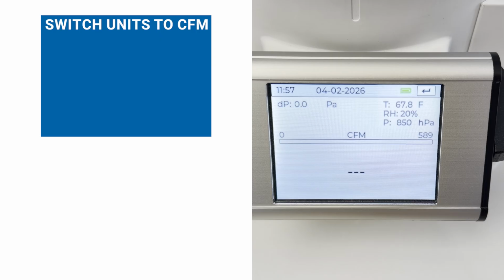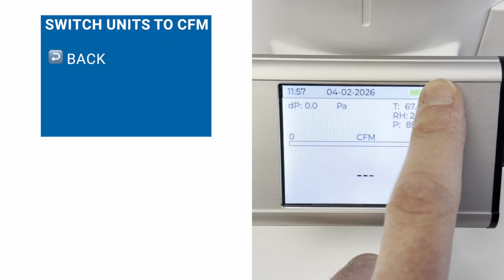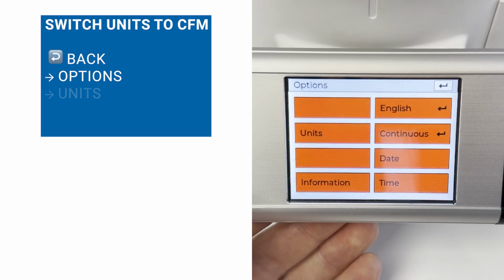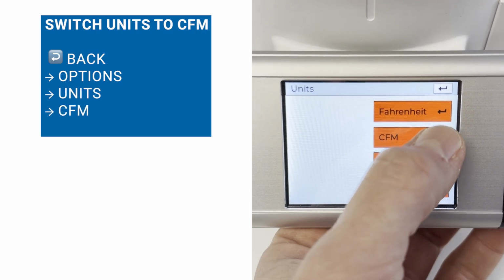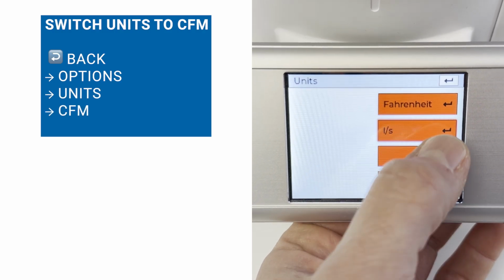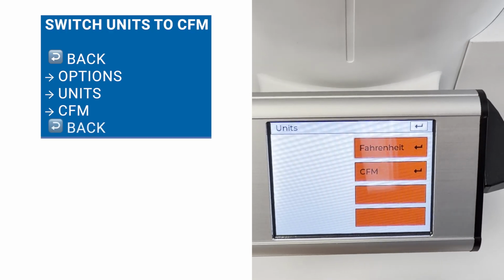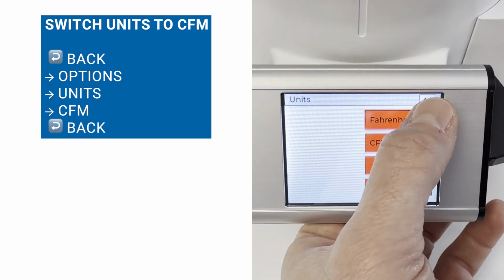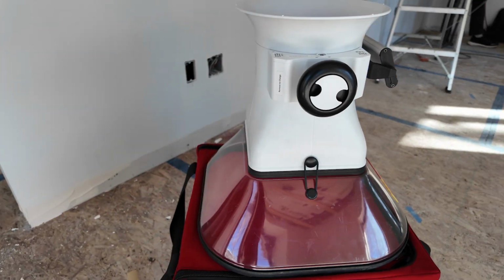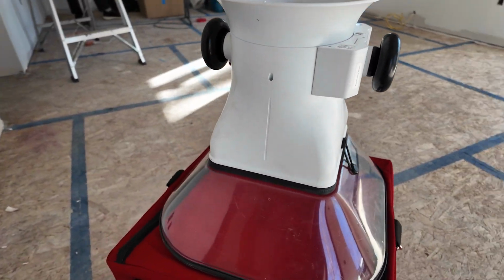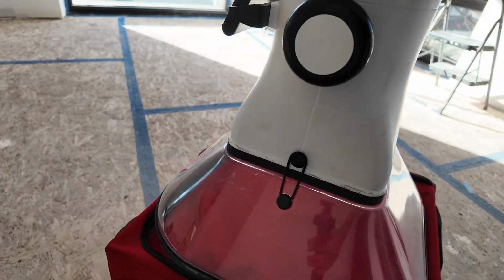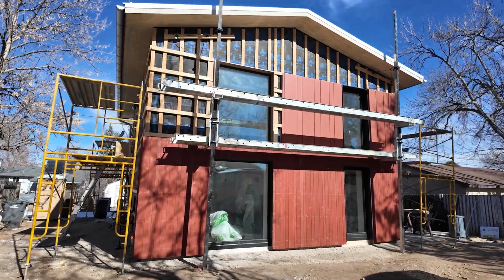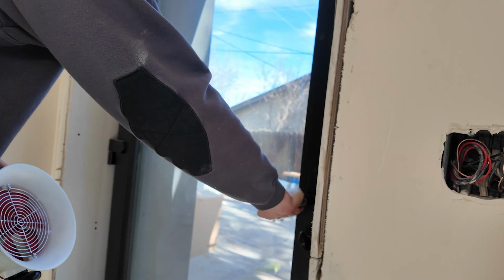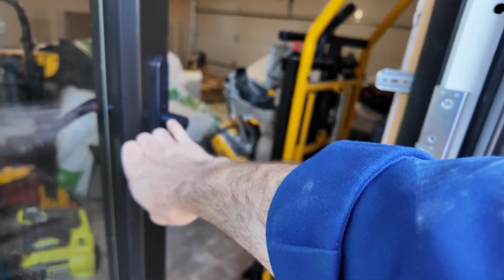Now we switch the units to CFM. Hit the back button again, go to Options, then Units. Select CFM as the commissioning sheet is set up to accept CFM. Now hit the back button. Make sure the 24-inch hood attachment is always on the flow finder when making measurements. Before you start taking measurements, make sure everyone on site knows to keep windows and outside doors closed. Hang a sign if necessary. Now we're ready to measure.